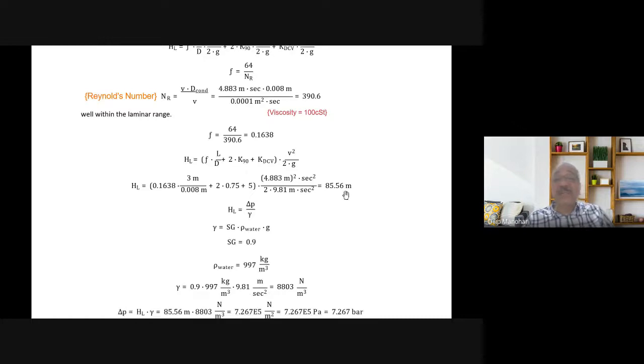So here we get a head loss in terms of oil column of roughly 85 meters. We calculate that and convert it into the pressure drop across the points PP to PA, that is, across the whole set of items from the pump end to the tubing end. So that pressure drop, delta P, is rho g h.